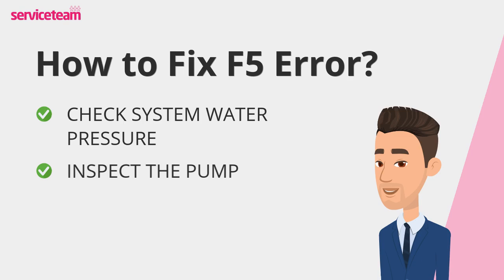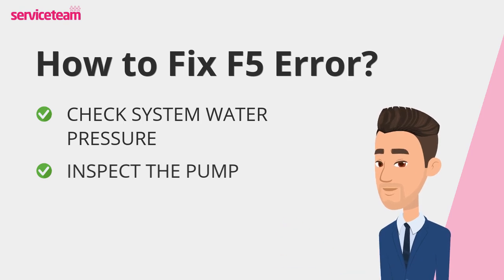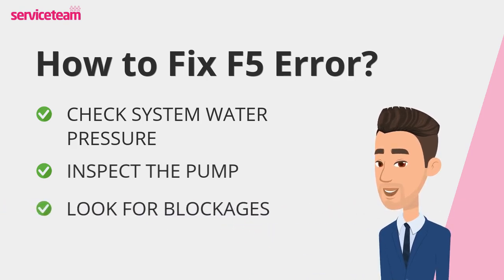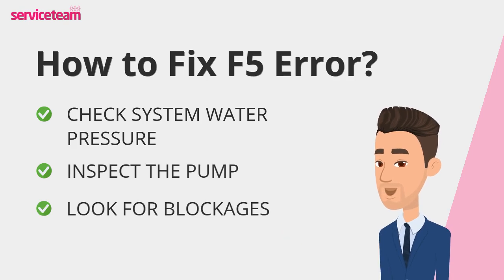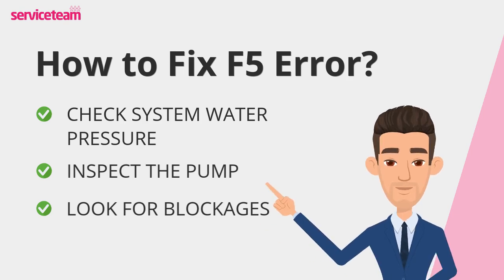Next, check the pump. A faulty pump can restrict water flow and cause overheating. Turn off the boiler and listen for unusual noises like grinding or banging from the pump. If it's not running smoothly, it may need professional servicing or replacement. Blocked pipes or heat exchangers can also trip your boiler. These blockages restrict water flow and lead to overheating — look for dirt or sludge in visible parts of the system. For serious blockages, call a professional for a power flush.